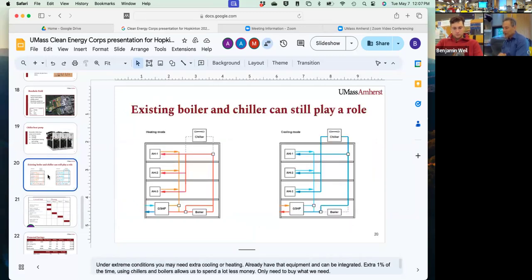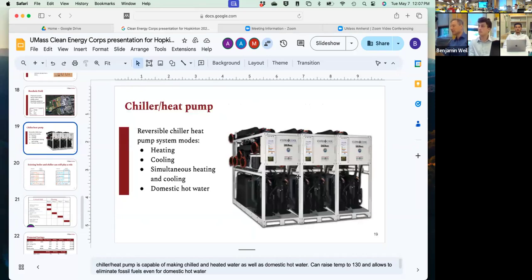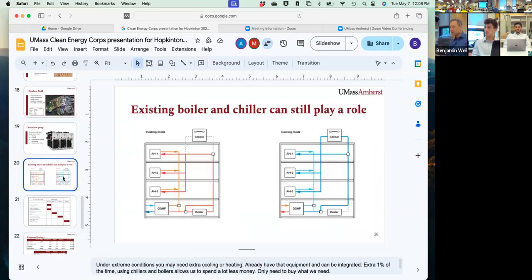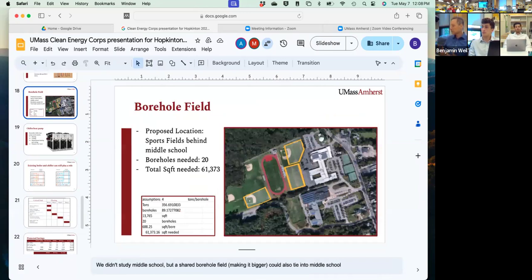The other upside is if you have insufficient capacity, but you've got your big chiller and it's modular, you can just add more. Let's say you needed, and I'm going to say it's probably going to be, 5 of these chillers lined up. They're all modular. And you add the middle school, you don't need to add 5 more. You probably need to add, say, 3 more. And now you have the capacity for 95% of the hours. That's going to satisfy both schools, no problem. And if you have an hour when things get really, really terrible, you just inject additional capacity from your existing boilers that you keep around, and your existing chiller that you keep around, and that minimizes the investment, right? Because we're talking about just a few hours per year that you might have an extreme condition. So by linking them, you get to spend less overall.